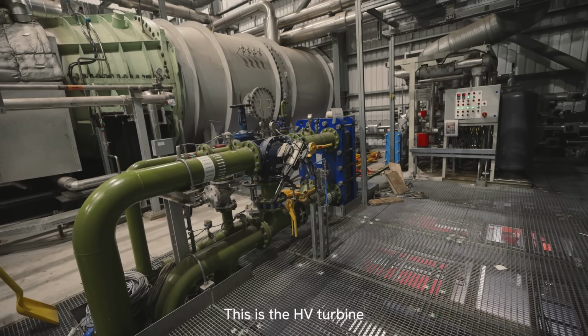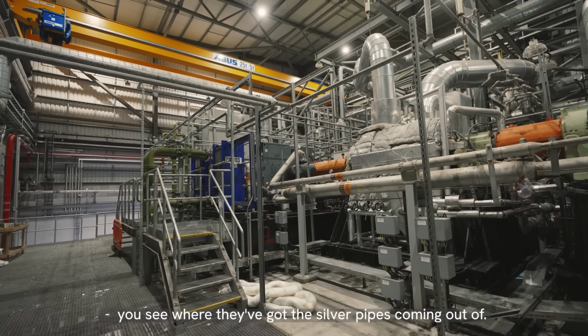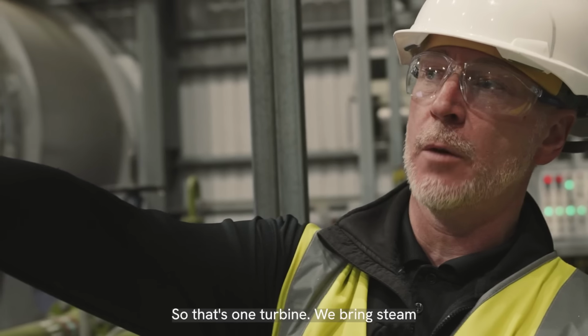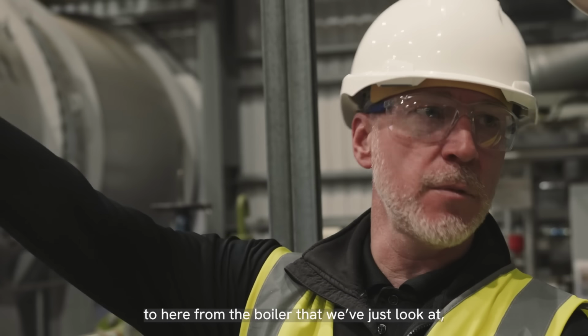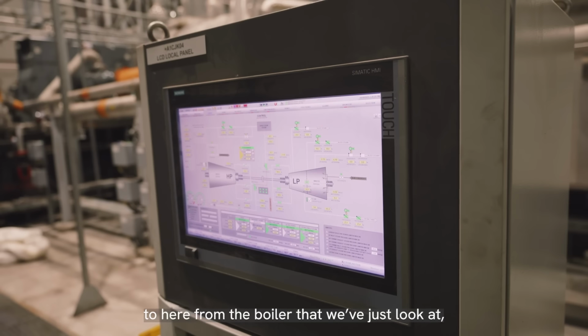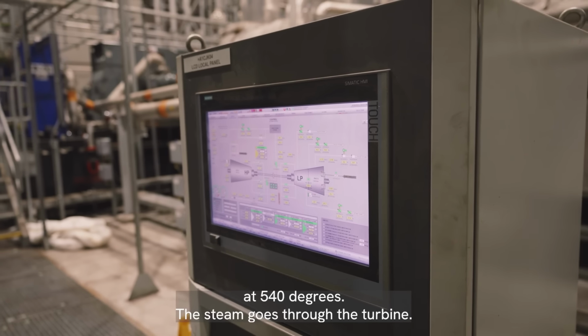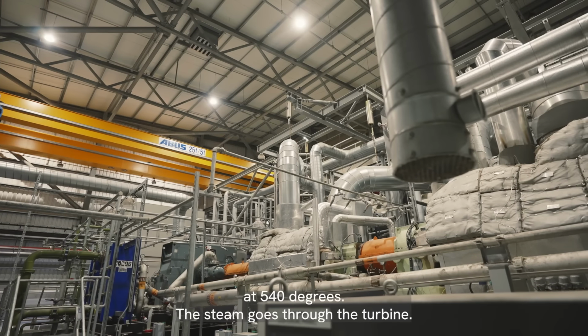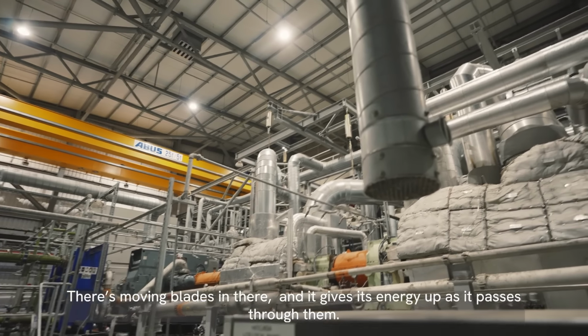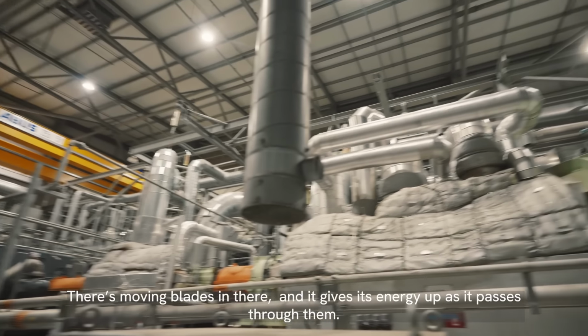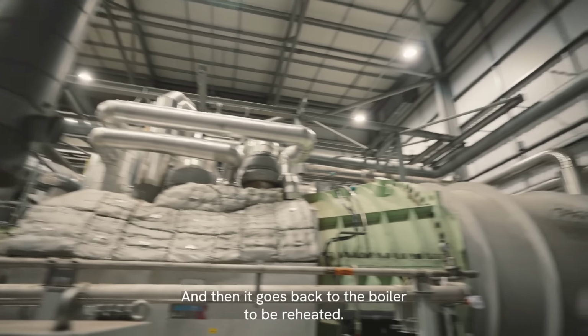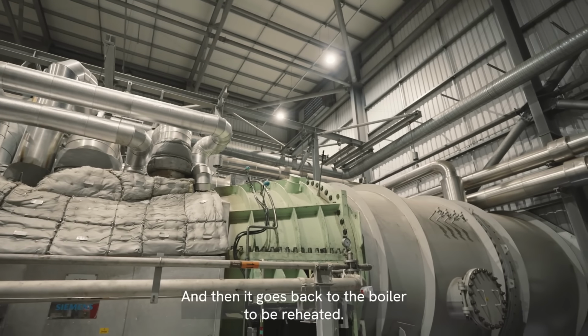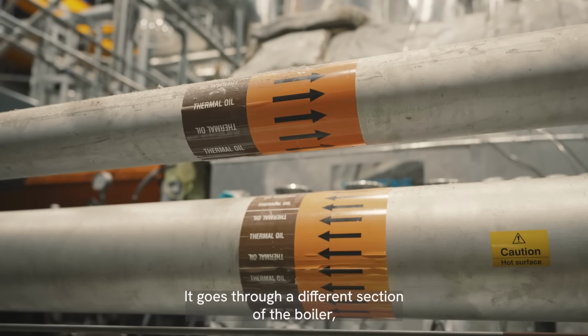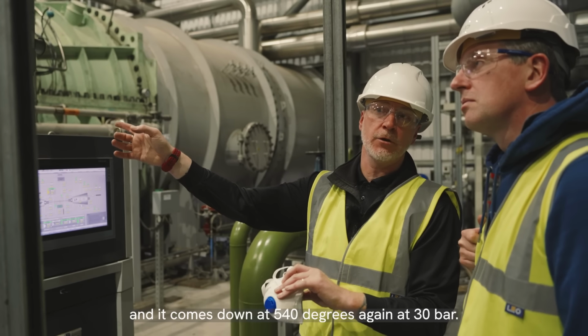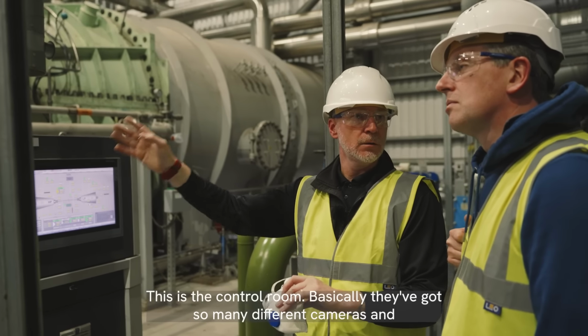This is the HP turbine. You see where they've got the silver pipes coming out? That's one turbine. We bring steam here from the boiler we've just looked through, at 540 degrees. The steam goes through the turbine - there's fixed and moving blades in there, so it gives up its energy as it passes through them. Then it goes back to the boiler to be reheated, through a different section of the boiler, and it comes down again at 540 degrees, 30 bar.